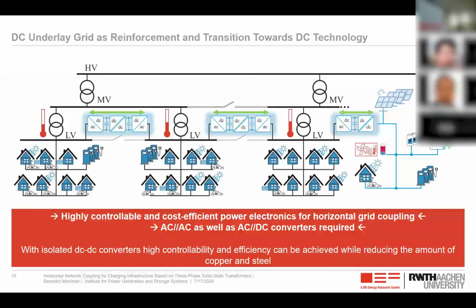And we can also go one step further by using the same technology to build up a DC grid. And this is what we call an underlay DC grid. And this allows us to realize all the advantages of the DC grid, such as lower losses, lesser material consumption, simpler control, and increased efficiency due to the elimination of inverter stages. And in order to achieve this, we need highly controllable and cost-efficient power electronics. And in the further course of this presentation, I will show how we can achieve this by using conventional and standardized power electronic building blocks.